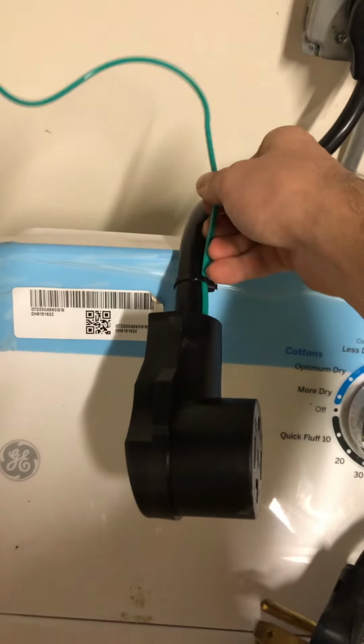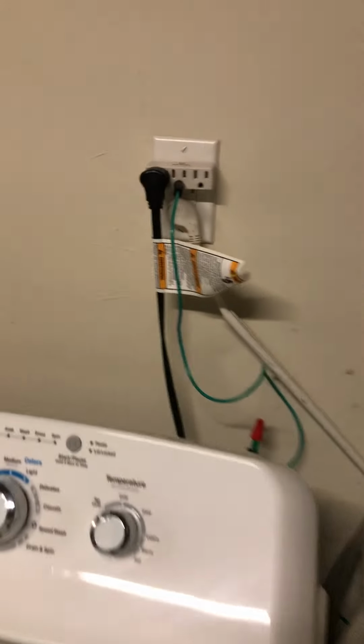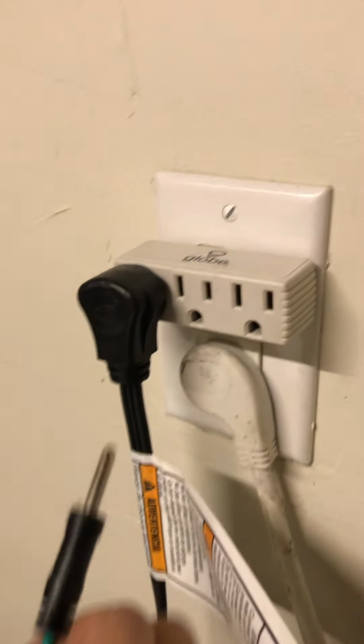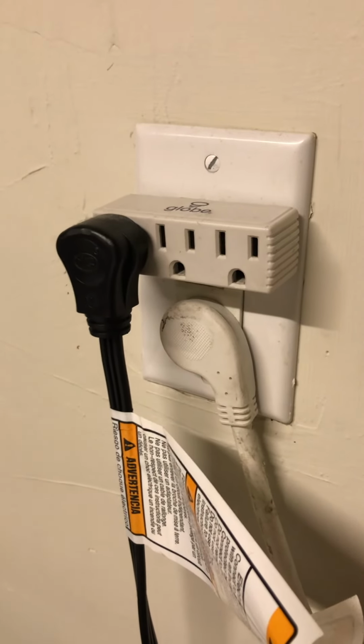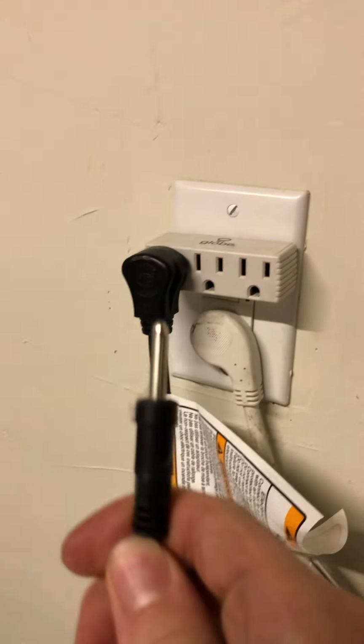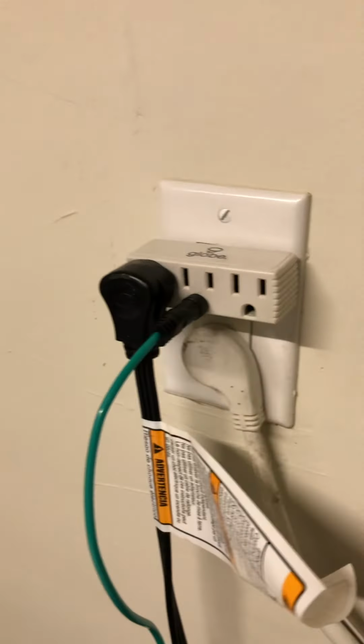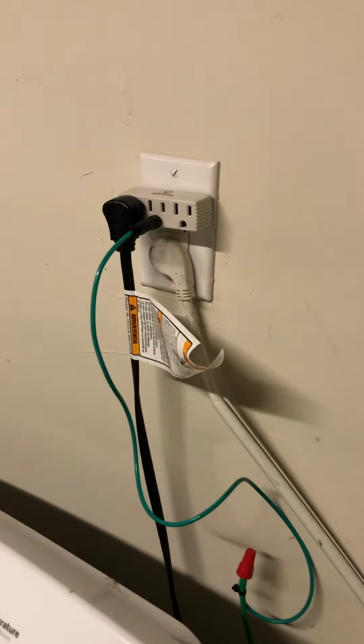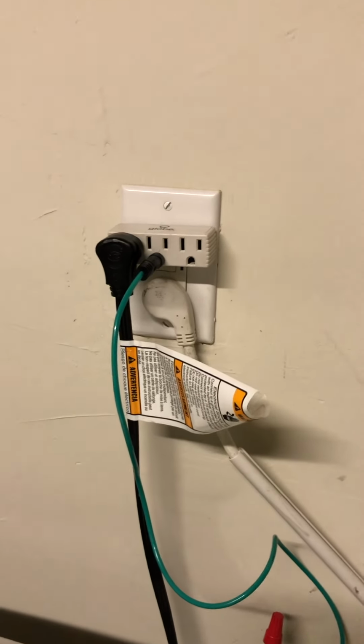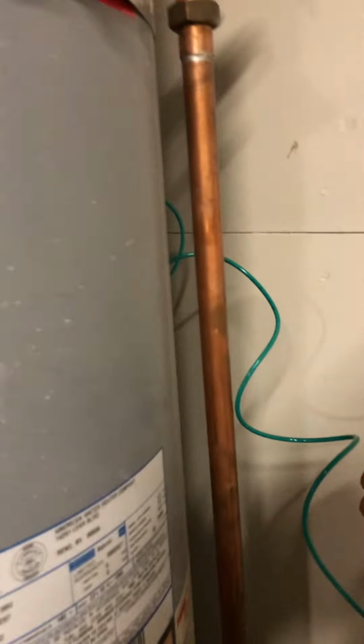4-prong to 3-prong adapter plus a ground. So to be safe, they give you this extra wire that you're supposed to run over to your standard, I think that's a NEMA 5-15 receptacle. So you take the ground, plug it in there. The only thing that's a little bit fishy is that that's a 15 amp circuit, but that receptacle is 30 amps, so you could have a 30 amp surge to ground, and I don't know if the wiring is rated for that 30 amps.